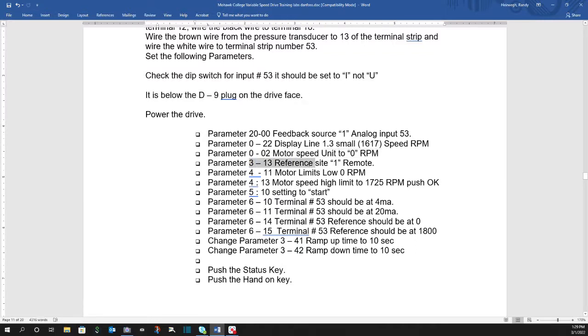Here we have to change the reference site. In other words, the signal, what's it going to do? Does it need to be hand? Does it need to be linked to auto? Obviously, we want it in remote so that when we hit the auto on and give it a digital command from my little switch, it's going to run based on the current draw, or current output, I apologize, of my transducer. Okay, so these are all pretty straightforward things to do.